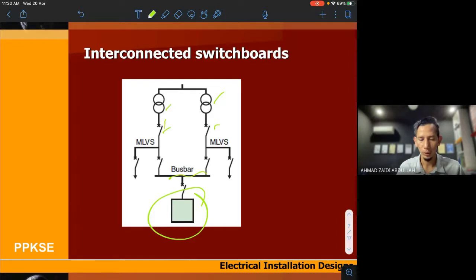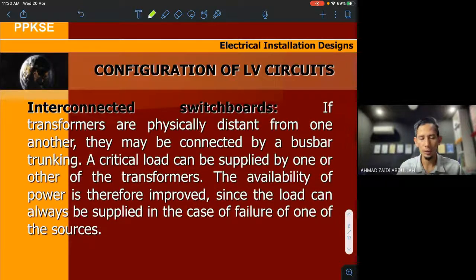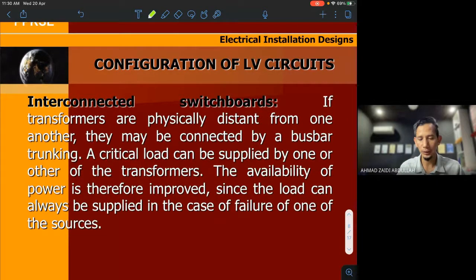So, you have a lot of breakers here. So this configuration we call it interconnected switchboard. So very good system. So if transformers are physically distant from one another, they may be connected by a bus bar trunking. A critical load may be supplied by one or other of the transformers. The availability of power is therefore improved, right?